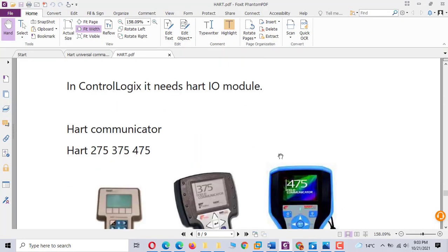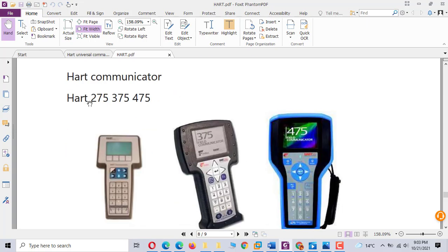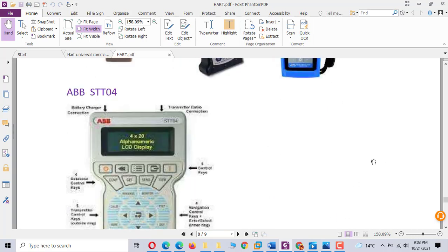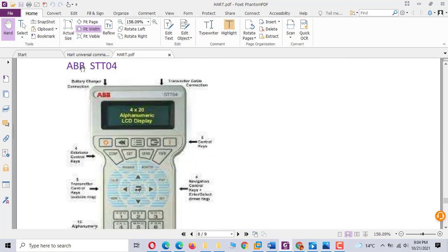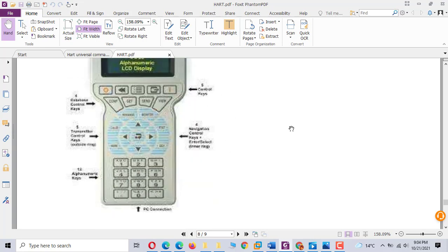Okay. For the Hart communicator, the most used is the Hart 275, which is the old one. The 375 is out of date. It's the 475 now, and the 475 is very popular. There is also the ABB STT04, which is out of date but still very powerful. Before, I used this one for calibration of pressure transmitters and temperature transmitters.